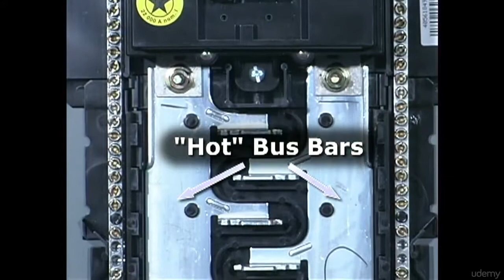Just to elaborate a bit on panel locations and main breakers, like what you see in that video: often the panel is not outside, as it is in this case, and often it's not a combination meter center where the meter, main, and branch circuits are all in one location outside the home. In many areas, the panel is actually in the basement or the garage, and outside the house you'll see the meter. From the meter it goes to your main panel, through the main breaker, and then to the branch circuits—and that panel could be anywhere.